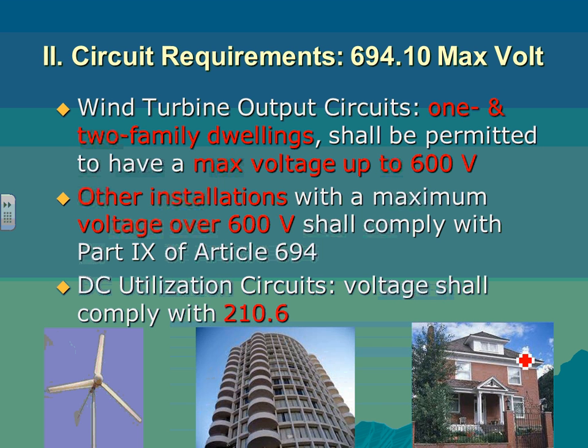But the electrician guys, have you done medium voltage higher than 600 volt? Anybody? If you go higher than 600 volt, then the equipment has to be listed for high voltage. So they refer you to this section 9 of Article 694, which tells you, by the way, if your panel is generating at 1200 volt, that's higher than 600 volt. Your equipment has to be listed for high voltage equipment, meaning the insulation is higher, and they refer you to a different article that talks about insulation, design and construction for higher than 600 volt, which is bigger equipment, a little bit more robust design.